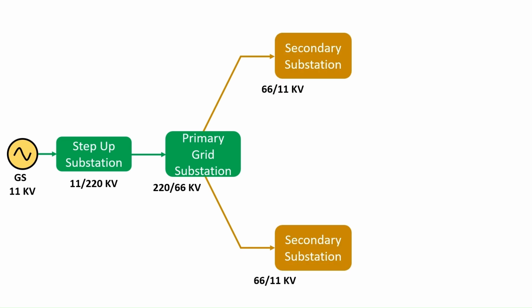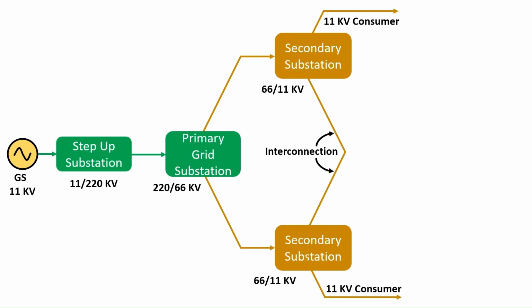From the primary grid substation, electric power is transmitted at 66 kV by a three-phase three-wire system to various secondary substations located at strategic points in the city. At a secondary substation, the voltage is further stepped down to 11 kV. The 11 kV lines run along the important roadsides of the city. It may be noted that big consumers having demand of more than 50 kilowatt are generally supplied power at 11 kV for further handling with their own substations. The secondary substations are also generally of outdoor type.